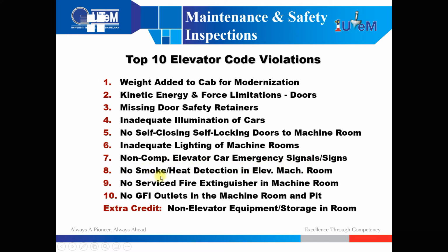And then no smoke or heat detection in elevator mechanical room. No service fire extinguisher in machine room. Okay, no GFI outlets in the machine room and pits. Okay, non-elevator equipment or storage in room. This one is related to the machine room lah. Di bahagian machine room di mana kena ada smoke detector, kena ada fire extinguisher. Okay, perlu dilengkapi dengan safety features lah.